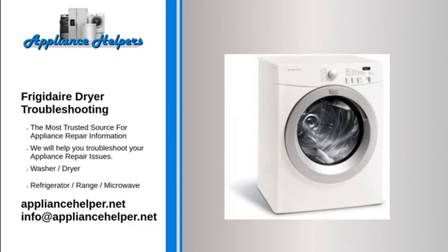Use an approved vent hood with a swing-out damper that opens when the dryer is in operation and closes automatically when the dryer stops. Do not attach a screen over the vent hood opening, and maintain a minimum clearance of 12 inches between the bottom of the vent hood and the ground. Be sure you're connected to a 240-volt circuit. Using 208-volt can increase drying times. Refer to the installation instructions.